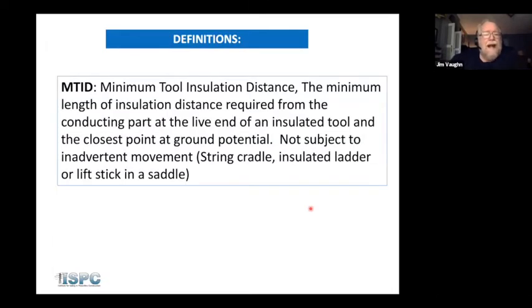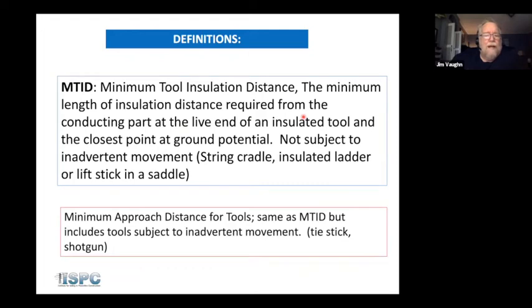MTID. Not going to spend a lot of time on this because we actually use MAD for the most part. But if you're working in bare hand work, MTID is a consideration depending on how you might be using ladders. That's the minimum tool insulation distance, or the minimum length of insulation required from the conducting part live end of an insulated tool to the closest point at ground potential. So this would be a ladder fastened to the structure that the lineman moves out on, and he has to get at least MTID or MAD away from the structure before he enters MAD coming in the other direction. We're not going to spend any time on transmission like that, but just to give you an idea where MTID might be used.